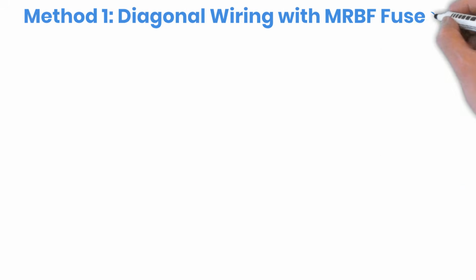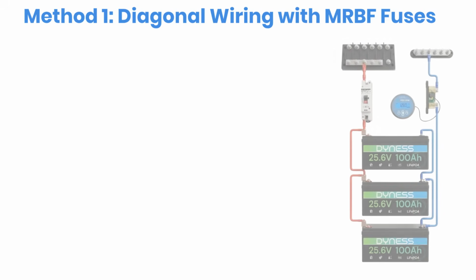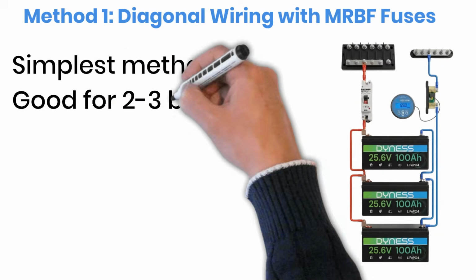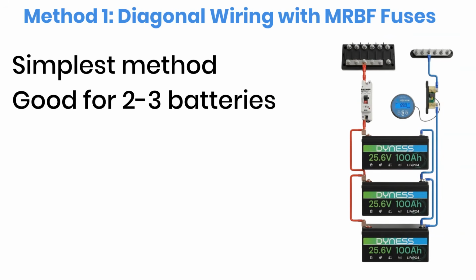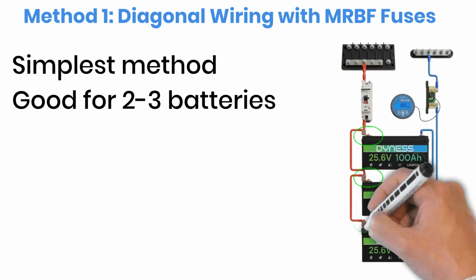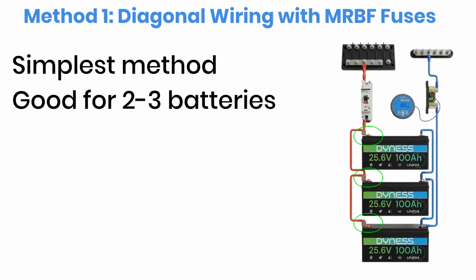This is probably the simplest approach, especially if you're only connecting 2 or 3 batteries. With this setup, an MRBF fuse is mounted directly onto the positive terminal of each battery. From there, each battery is connected individually to the main bus bars using its own cable. It's a very clean layout, it's easy to understand, and troubleshooting is usually straightforward because every battery has its own dedicated connection. To help the batteries share the load more evenly, it's good practice to take the main positive connection from the first battery and the main negative connection from the last battery. This encourages a more balanced current flow across the battery bank instead of placing more demand on just one battery.